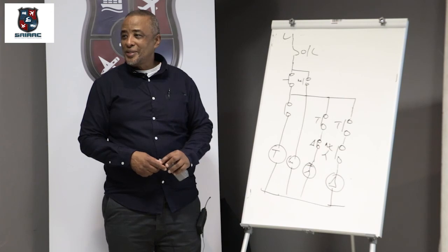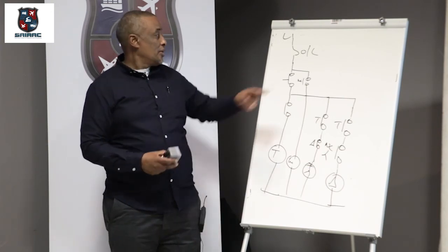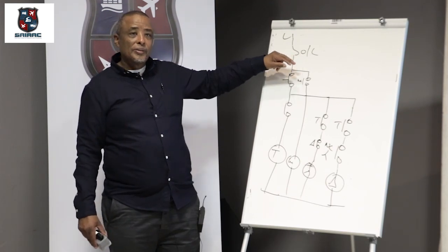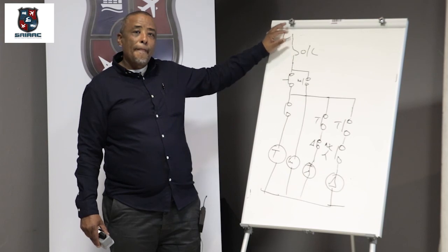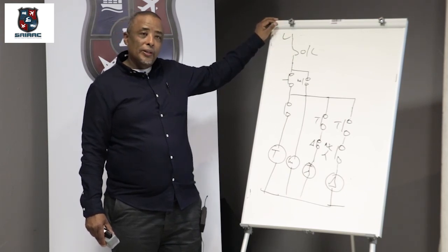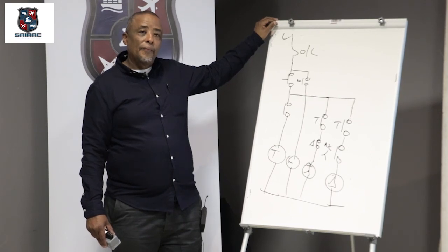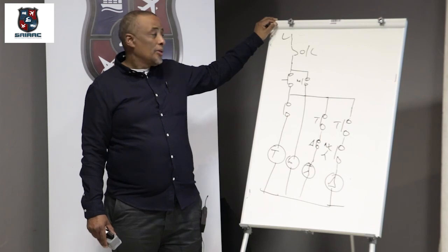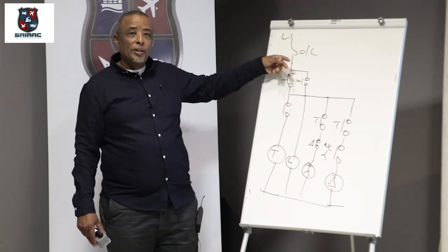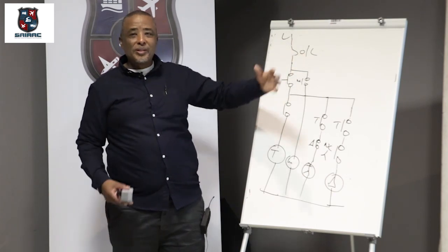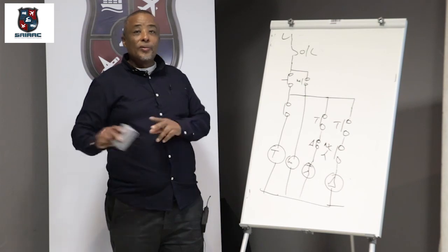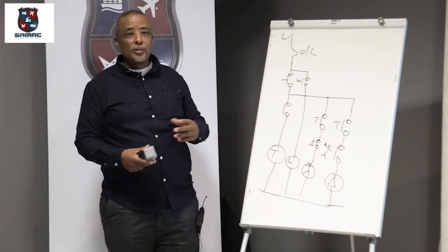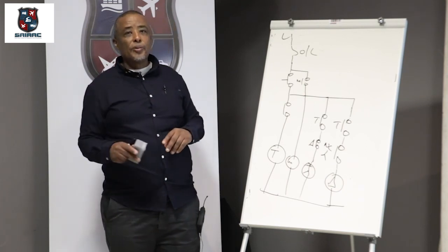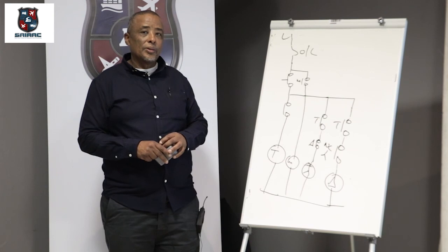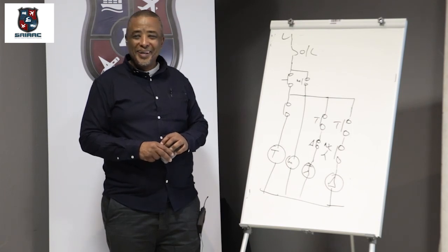You okay? Star-Delta starters? So if you have an overload situation, here's your overload will trip out. But now the signal, say, in the plant room or whatever, it's called the mechanical overload. Okay. Any fans or too much load. How do we bring that mechanical overload signal? Where would we also bring it? Just bring it in series. In series with that, yeah. All your controls, whatever sensors, safety sensors, whatever you have, put them all in series with that. One packs up, automatically kill the circuit until you find the fault. Normally on your PLC, you'll be able to see on the screen, there's the problem there, there's the problem there. Okay. All right. I know it was a bit rushed.